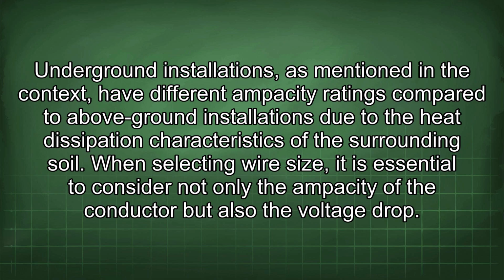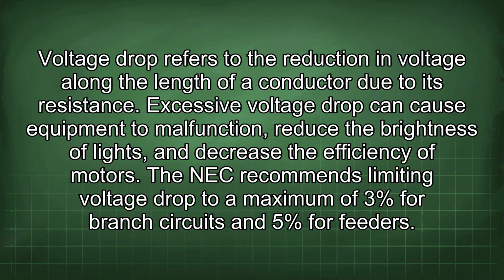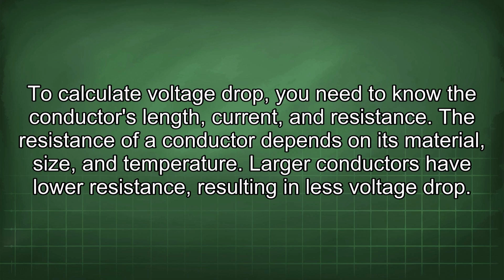When selecting wire size, it is essential to consider not only the ampacity of the conductor but also the voltage drop. Voltage drop refers to the reduction in voltage along the length of a conductor due to its resistance. Excessive voltage drop can cause equipment to malfunction, reduce the brightness of lights, and decrease the efficiency of motors. The NEC recommends limiting voltage drop to a maximum of 3% for branch circuits and 5% for feeders. To calculate voltage drop, you need to know the conductor's length, current, and resistance. The resistance of a conductor depends on its material, size, and temperature. Larger conductors have lower resistance, resulting in less voltage drop.